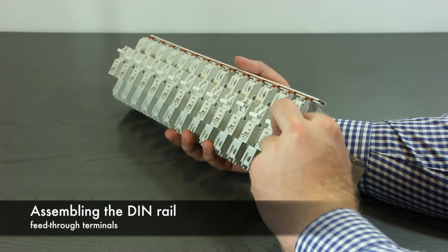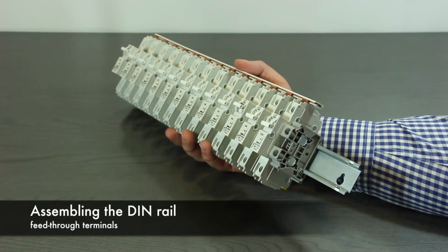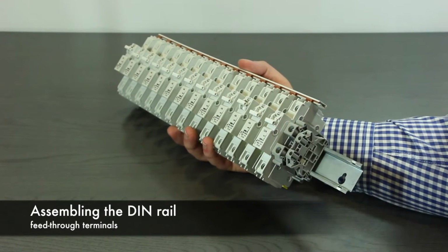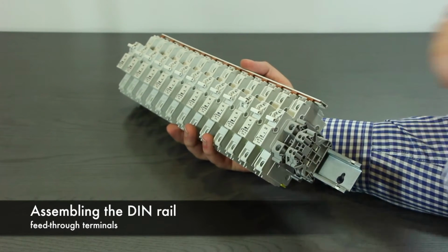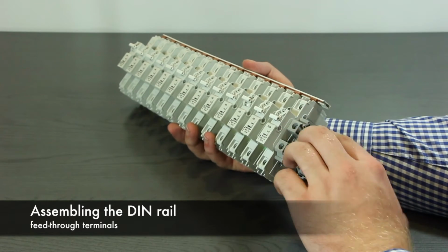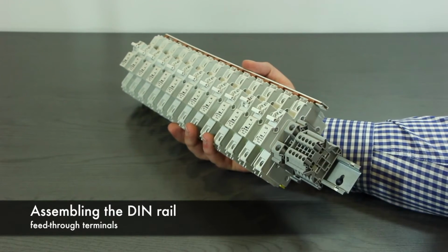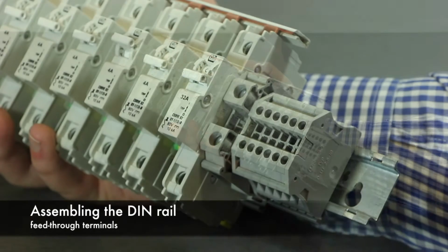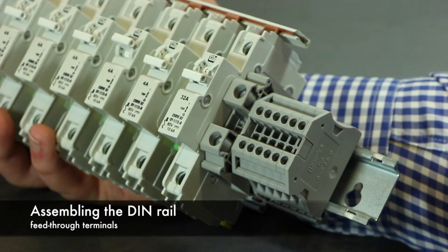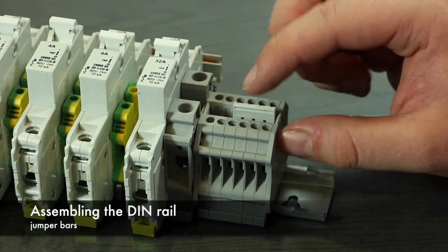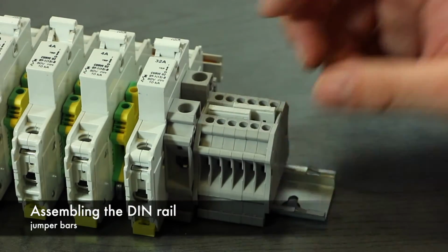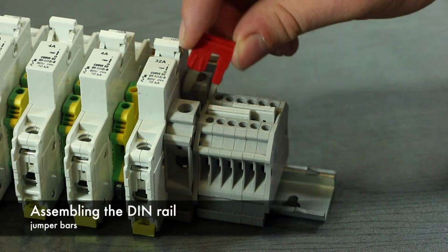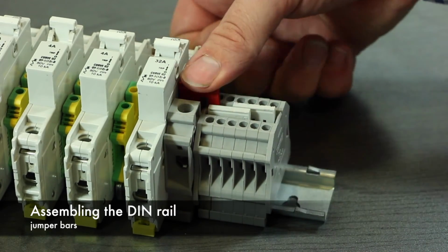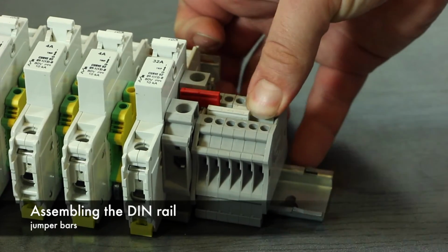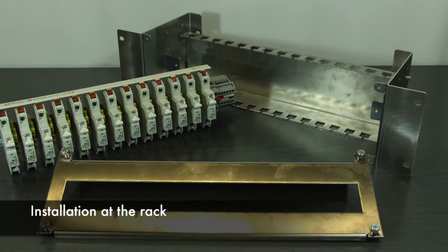Finally, mount the feed-through terminals on the DIN rail by snapping them in. Place the large feed-through terminal at the last circuit breaker with the cover plate attached. Now mount the small feed-through terminals without any clearance to the large feed-through terminal, finishing with the cover plate. Connect the large feed-through terminal with the small ones using the red jumper bar. Connect the small feed-through terminals with the gray jumper bars, 1 at each end of the terminal row. The DIN rail is now complete and we can proceed with the installation at the rack.